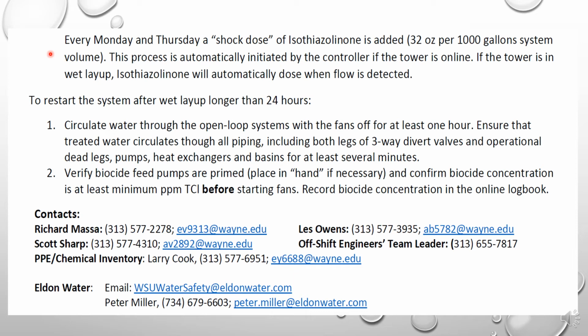If the tower is in wet layup and you haven't initiated that circulation yet on a Monday or Thursday morning, the isothiazolone will then dose once it detects flow through the controller. To actually restart your system after a wet layup longer than 24 hours, you want to circulate through the open loop systems with the fan off for at least 1 hour. You want to ensure that your water circulates through everything, just like in wet layup. You want to verify that your pumps are primed, and you want to confirm the biocide concentration is at least the minimum total chlorine before you start your fans.